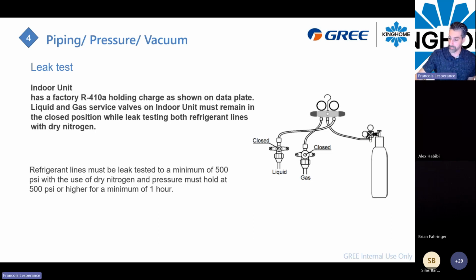Okay, so moving forward, the pipe is already installed correctly. You will do your pressure test. Because we're using a service valve on the indoor unit and the outdoor unit, why not do your pressure test and all your vacuum directly inside the house? So you will not have to work outside if it's a bad temperature, rainy, cold, snowing, whatever.